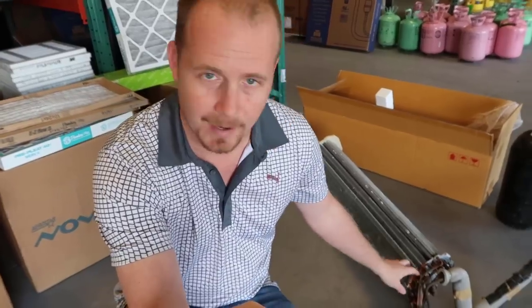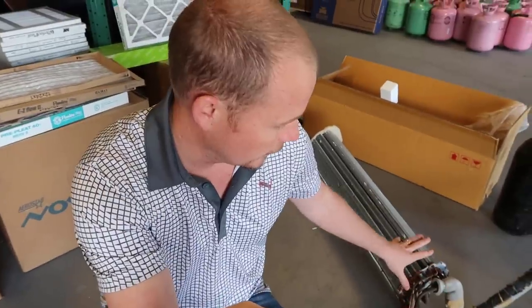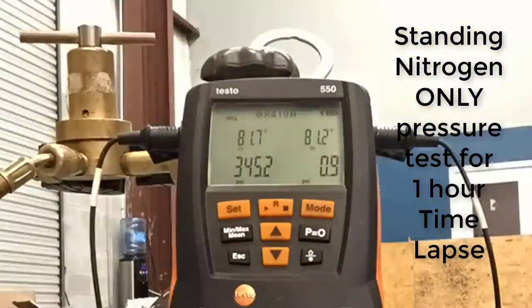We're doing a demonstration because we're doing a leak detection on a ductless evaporator coil that we just got in. We found a leak on it, and I don't find a lot of ductless evaporator coil leaks, so I wanted to verify the leak location. I also wanted to show the H10G — we have an old H10G here — and show its performance against the new Testo leak detector that I just got and see what we find out. We're working with 410A refrigerant.